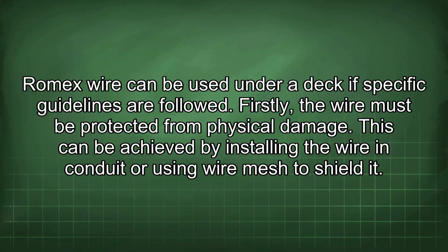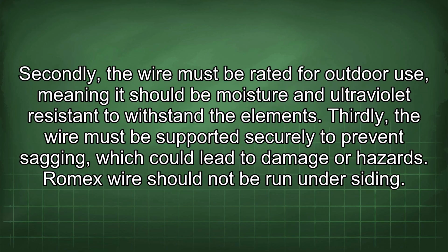Romex wire can be used under a deck if specific guidelines are followed. Firstly, the wire must be protected from physical damage. This can be achieved by installing the wire in conduit or using wire mesh to shield it. Secondly, the wire must be rated for outdoor use, meaning it should be moisture and ultraviolet resistant to withstand the elements. Thirdly, the wire must be supported securely to prevent sagging, which could lead to damage or hazards.